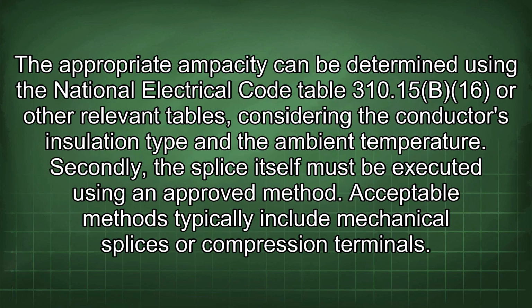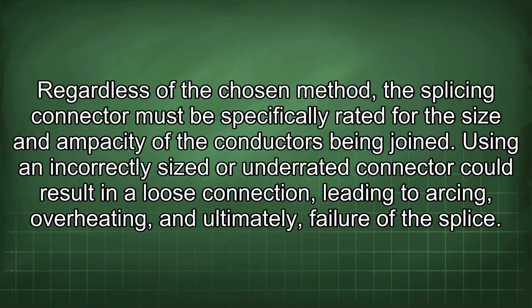The appropriate ampacity can be determined using the National Electrical Code Table 310.15(B)(16) or other relevant tables, considering the conductor's insulation type and the ambient temperature. Secondly, the splice itself must be executed using an approved method. Acceptable methods typically include mechanical splices or compression terminals. Regardless of the chosen method, the splicing connector must be specifically rated for the size and ampacity of the conductors being joined. Using an incorrectly sized or underrated connector could result in a loose connection, leading to arcing, overheating, and ultimately failure of the splice.